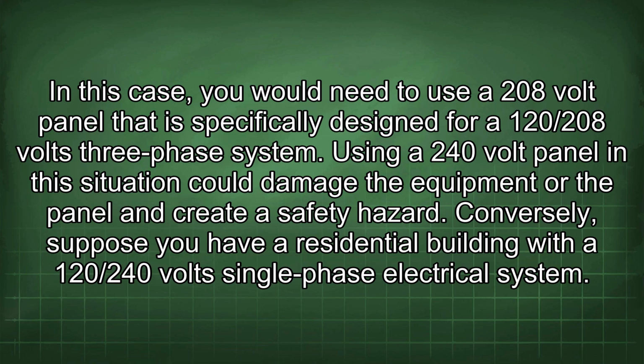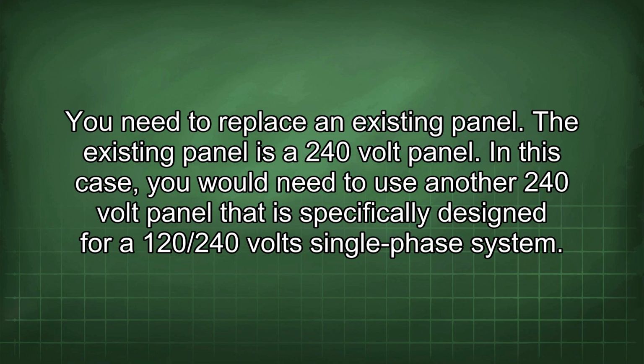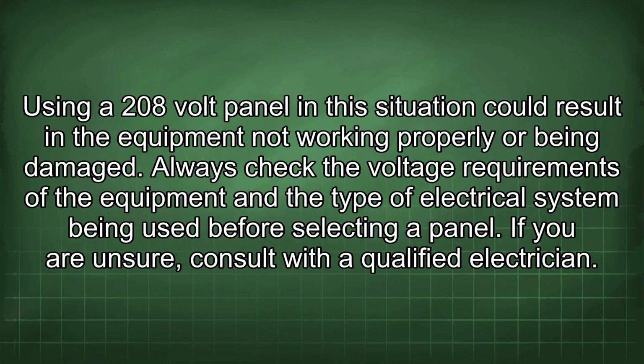Conversely, suppose you have a residential building with a 120/240-volt single-phase electrical system. You need to replace an existing panel. The existing panel is a 240-volt panel. In this case, you would need to use another 240-volt panel that is specifically designed for a 120/240-volt single-phase system. Using a 208-volt panel in this situation could result in the equipment not working properly or being damaged. Always check the voltage requirements of the equipment and the type of electrical system being used before selecting a panel. If you are unsure, consult with a qualified electrician.